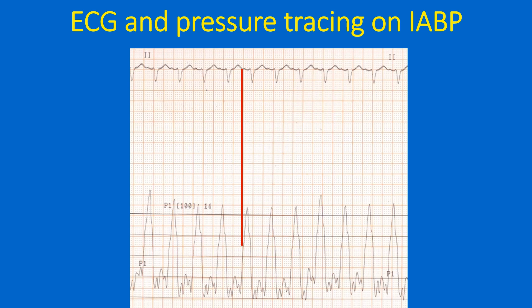Screenshot of the IABP screen. The uppermost green tracing is the electrocardiogram, which is used to time the inflation and deflation of the balloon. The augmentation time is marked just below the tracing to indicate the exact point of inflation and deflation. The arterial pressure tracing just below that indicates the diastolic augmentation.